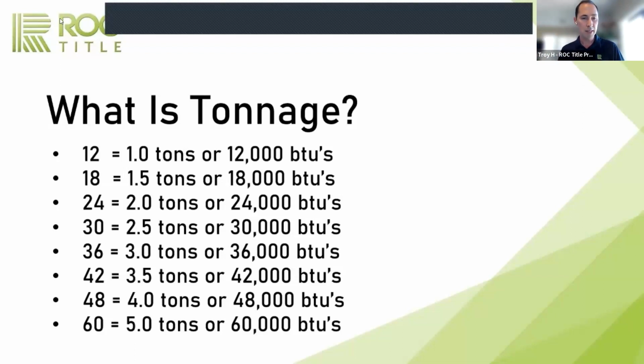When you see these numbers, 12 stands for the BTUs, 12,000, which equals 1 ton. So when you see numbers like 12, 18, 24, 30, 36, 42, 48, and 60, you always divide that by 12, and that will show you the size of it. On average, just rule of thumb, it's about 500 square feet per ton. So if you have a 1,000 square foot home, that's probably going to be a 2-ton system. In Phoenix, maybe a little more because of the intense heat, or up in Havasu or Vegas, or down in Tucson. I just wanted to explain that if you see those numbers.